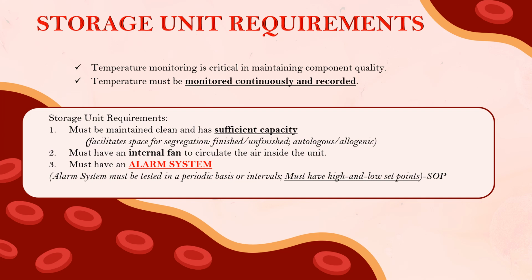You know, class, this alarm system is very loud, almost sounds like a siren or a time bomb timer, as I may describe it. This alarm sound, class, will not stop. It will only stop when the temperature has been corrected and turned back to the normal storage temperature. So it is also imperative that an alarm system must have high and low set points as per standard operating procedures.